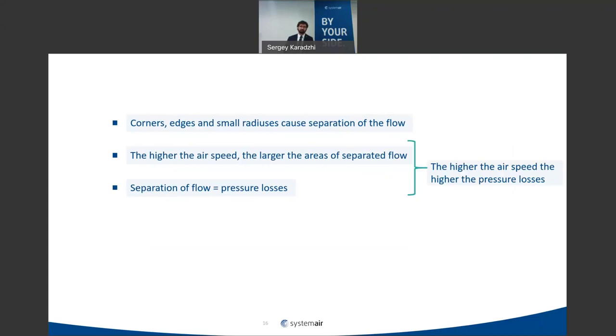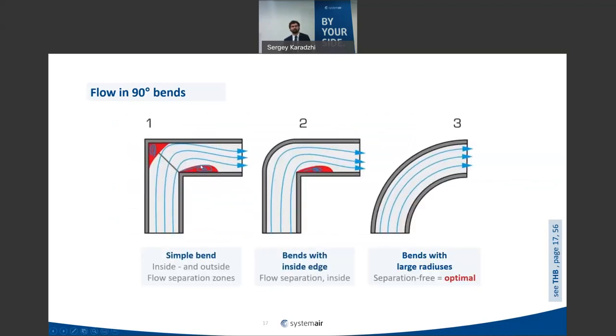For example, a 90-degree bend made without any radius creates separation in two places. A bend with radius only on the outer part and no inner radius still causes separation. If a fan is installed near such a bend, it will have significant problems. It's always better to use proper radii with low losses, so the fan doesn't need to compensate for additional pressure.